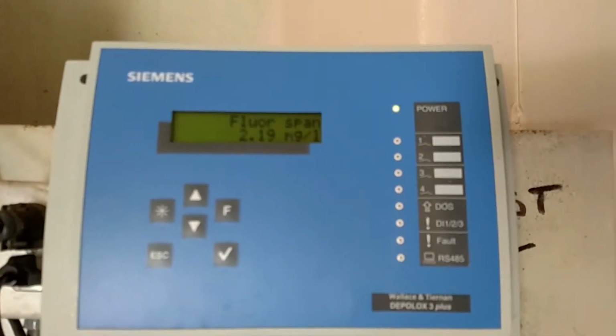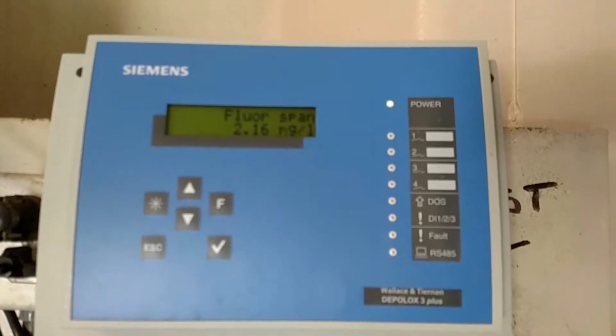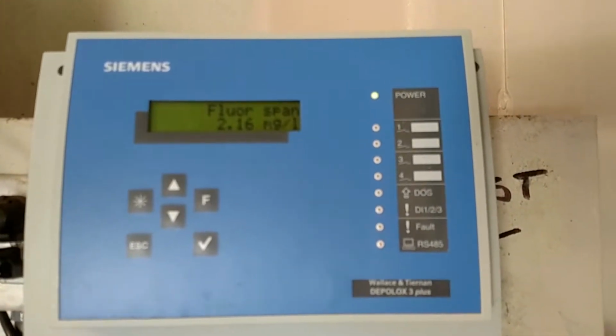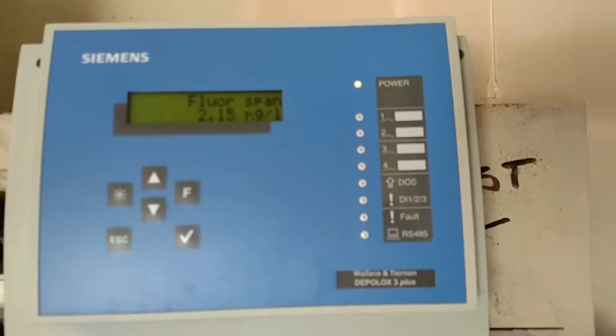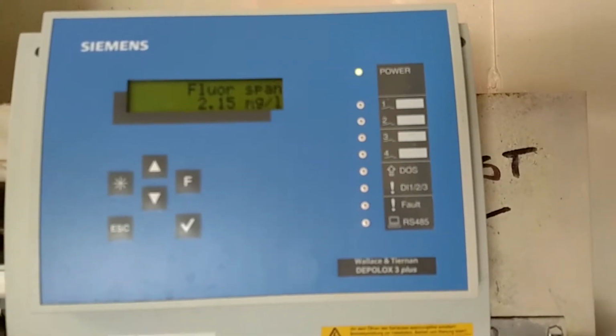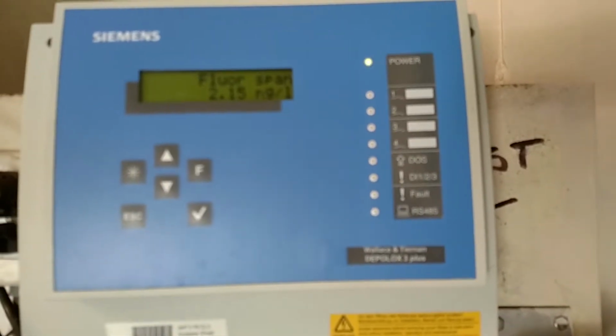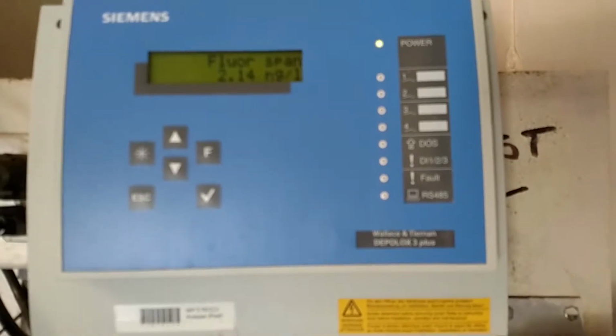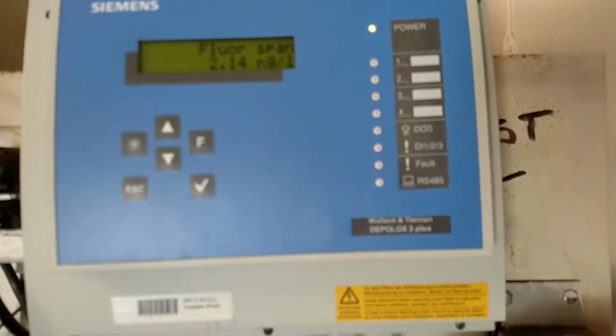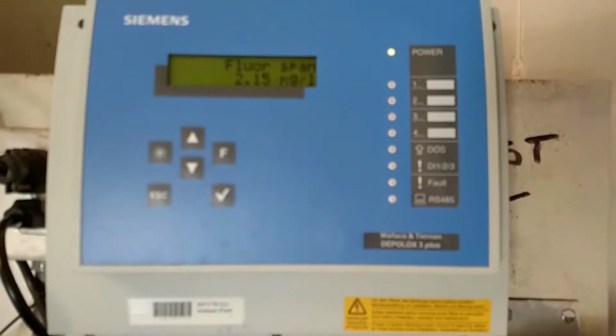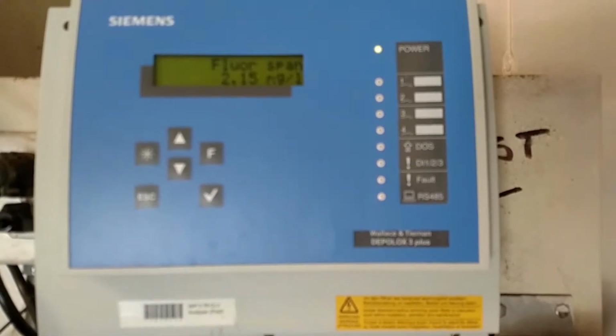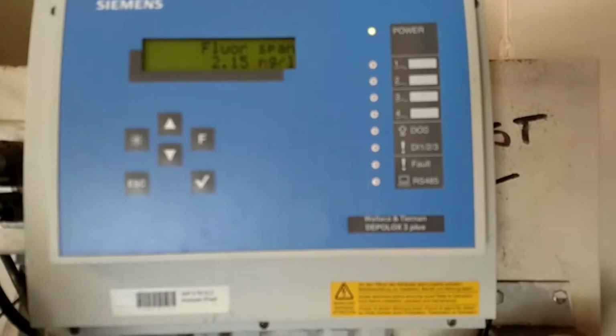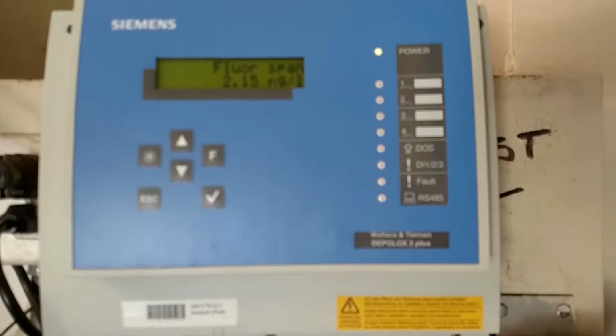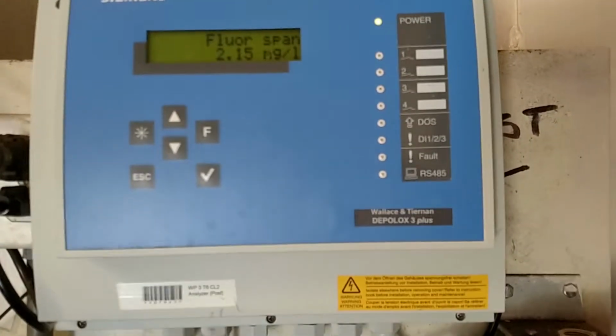Yes. I thought yesterday, because I had calibrated the pre, that by switching over to the post I would not have to recalibrate. But I had to recalibrate it again. Just different conditions in the water? Yes. Each analyzer is not conditioned, but each probe is a little bit different, and I calibrated it to that analyzer when the other one might actually be reading a little bit more or a little bit less as far as the millivolts.